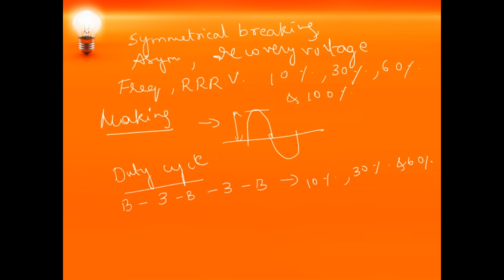The second test will be: break, after 3 seconds make, again break. This should be performed on not less than 100% of the rated symmetrical breaking capacity and not less than 100% of the rated making capacity. You have seen the ratings of the circuit breaker, is it not? During that time I told you about the duty cycle rating. So the same thing, whether after 3 seconds it is going to break or make, is tested for 10%, 30%, 60% and 100% of the capacity. That's all. Next is the short time current test, the last one.